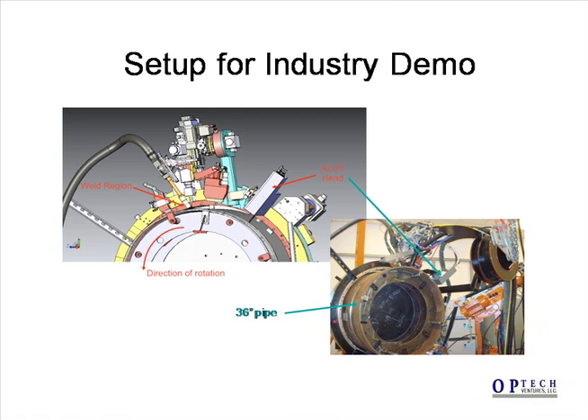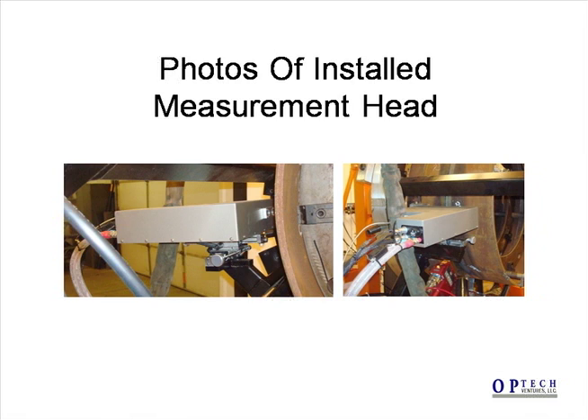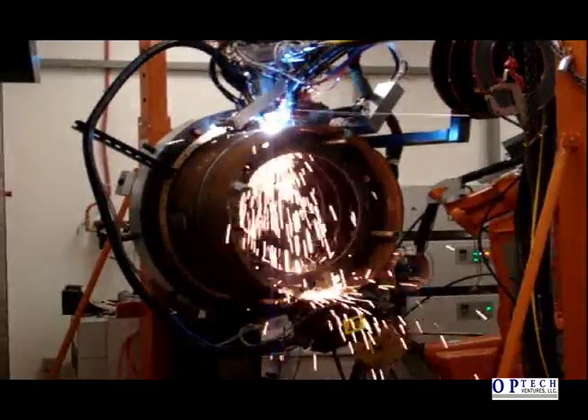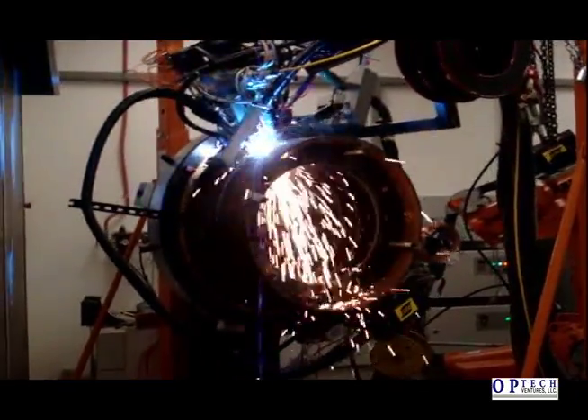We performed an industry demonstration at the site of the Weld Process Development Organization. The drawing and photo show a short section of pipe fixtured for welding by a hybrid laser arc process. The weld head is on top and the laser ultrasonic measurement head is at about the 4 o'clock position. Both heads are secured to a stage that rotates counter-clockwise during welding. The laser ultrasonic head is inspecting the weld about 5 seconds after it is formed. This is a video of the weld operation — the laser ultrasonic measurement head is acquiring weld data all the way around the pipe.